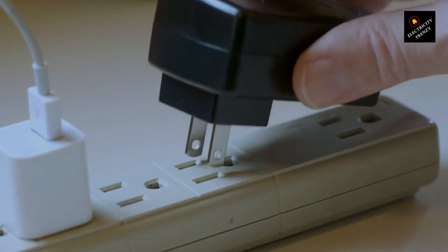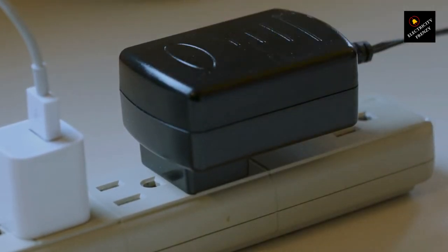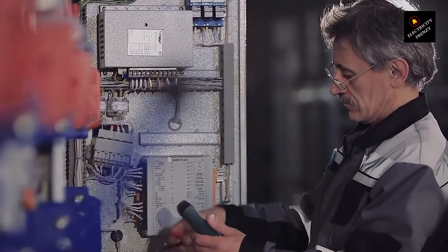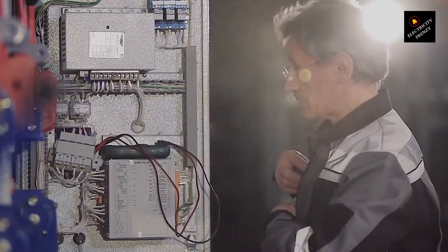Now, one common reason for a circuit breaker to trip is an overloaded circuit. That happens when the total electrical load exceeds the circuit's capacity. To check if this is the issue, unplug or turn off some devices on the circuit and see if the breaker still trips. This simple step can often solve the problem.